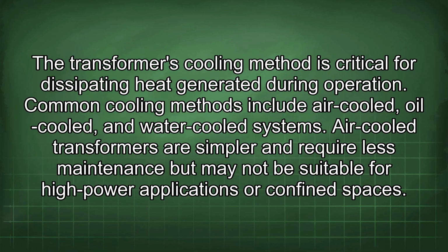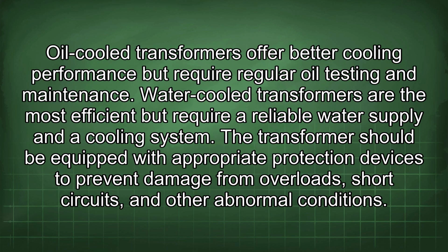The transformer's cooling method is critical for dissipating heat generated during operation. Common cooling methods include air-cooled, oil-cooled, and water-cooled systems. Air-cooled transformers are simpler and require less maintenance, but may not be suitable for high-power applications or confined spaces. Oil-cooled transformers offer better cooling performance, but require regular oil testing and maintenance. Water-cooled transformers are the most efficient, but require a reliable water supply and a cooling system.